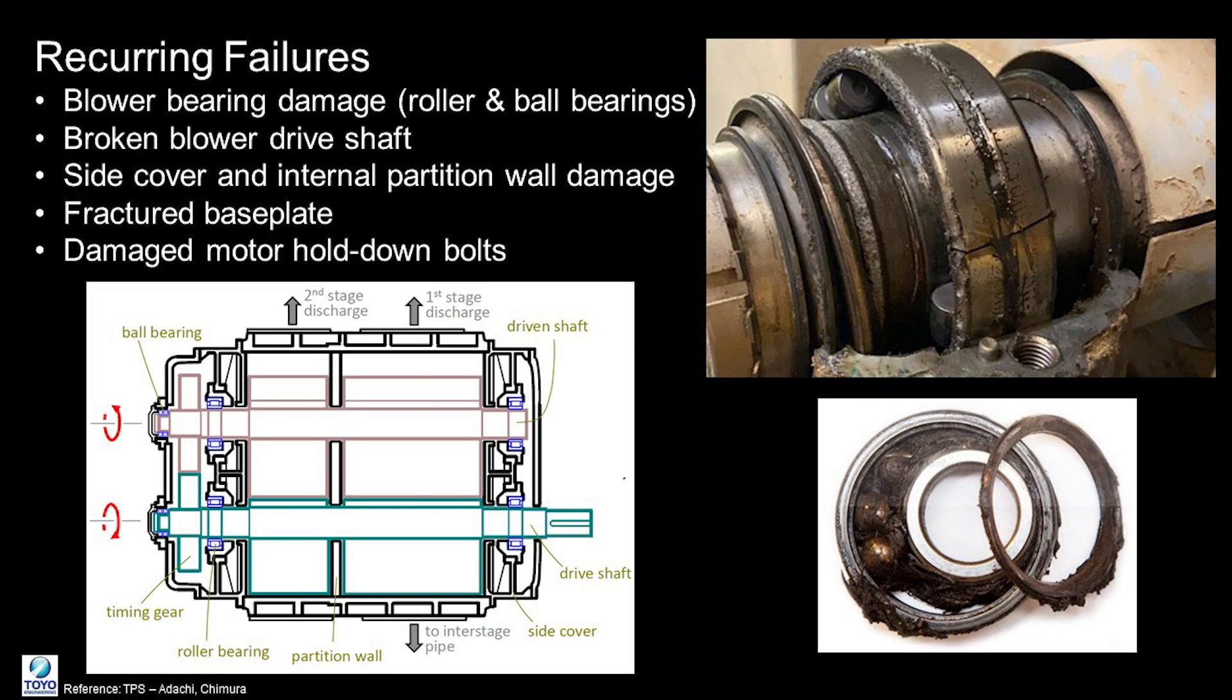This equipment experienced significant damage, including bearing failures, shaft breaks, and even fractured base plates, which were all linked to high vibration levels. These recurring failures prompted investigation to address the root causes.